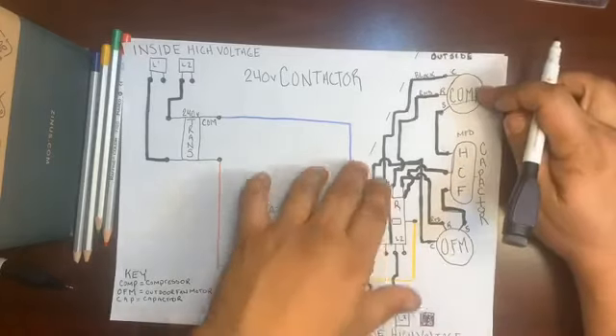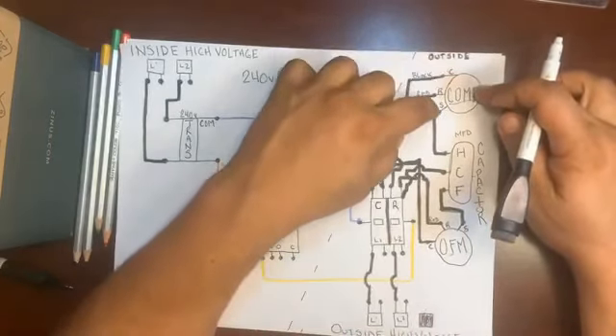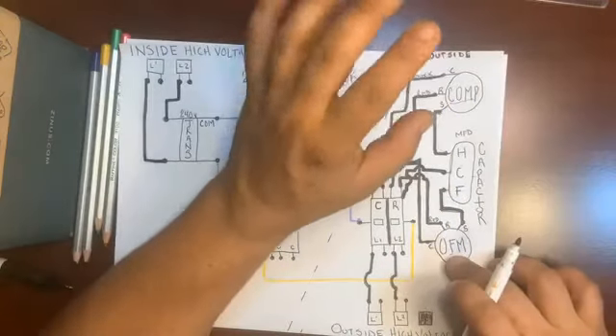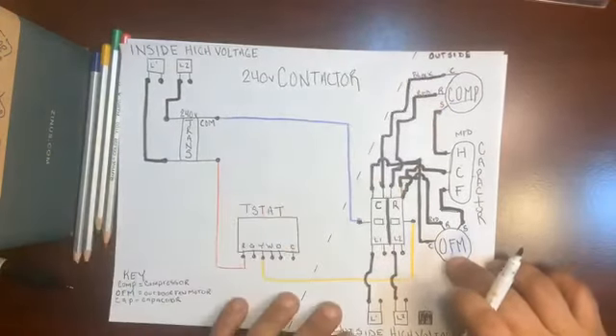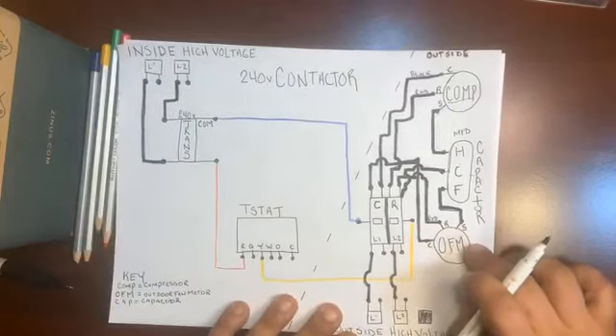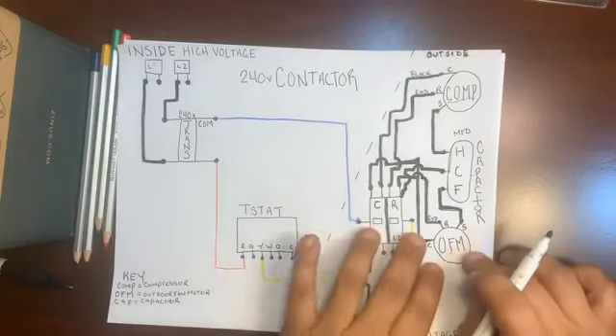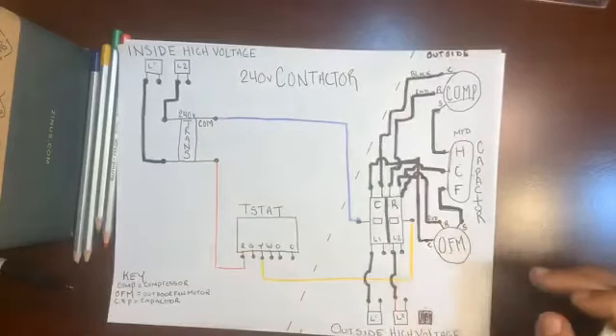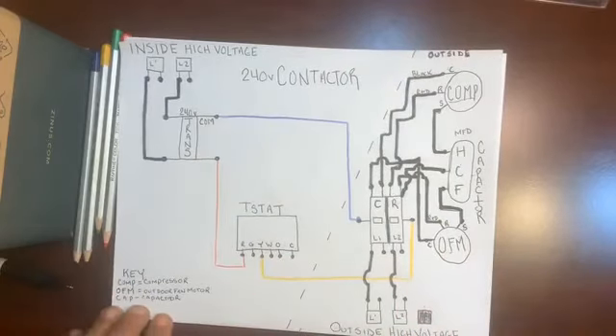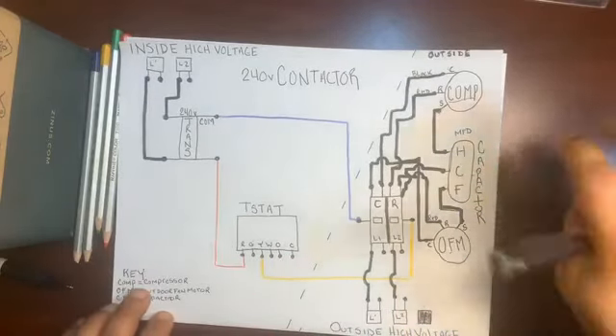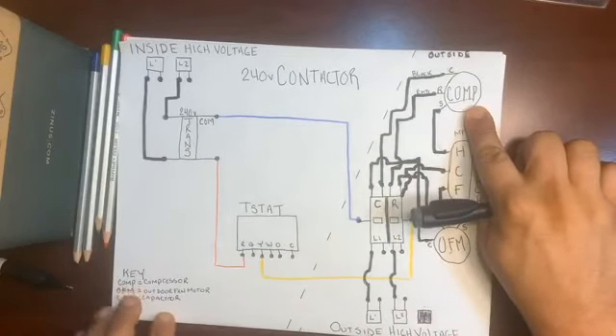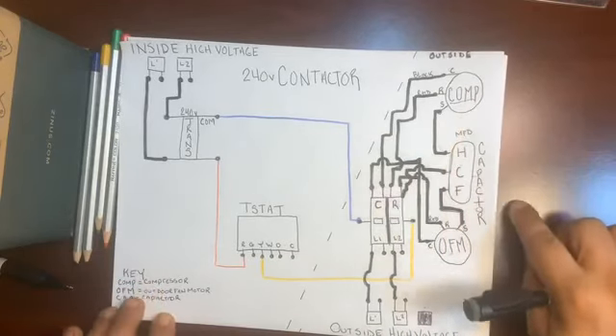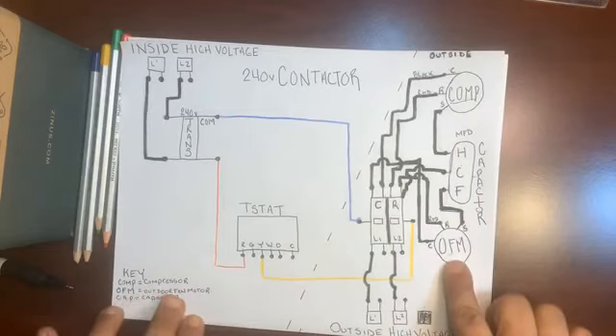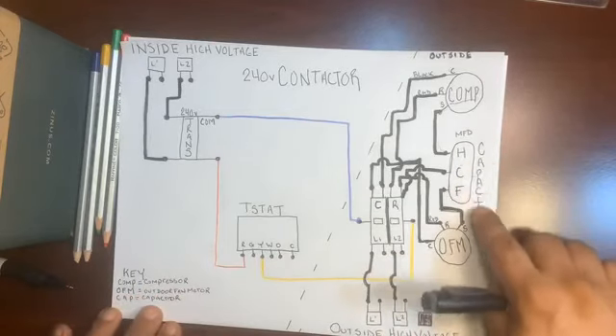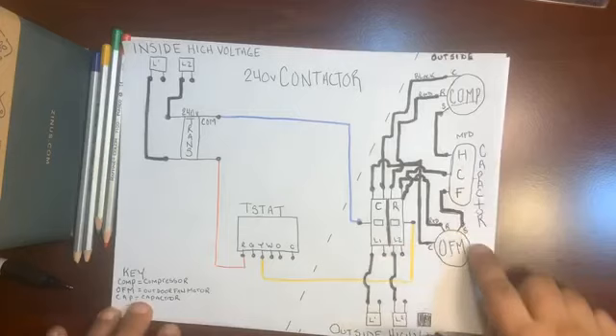Every compressor you come across in residential will have common, run and start. Every fan motor, OEM, which means a brand new one or one that was original to the machine, will have a common, run and start. We're going to get more and deeper into the fan motors and how deep they go. We have our key here, right? Our key. We had a few abbreviations here, COMP. Look into our key, COMP is compressor. We had OFM, outdoor fan motor, and then capacitor would be, if you just had a right cap, you could put capacitor down here. We'll do our line markings.